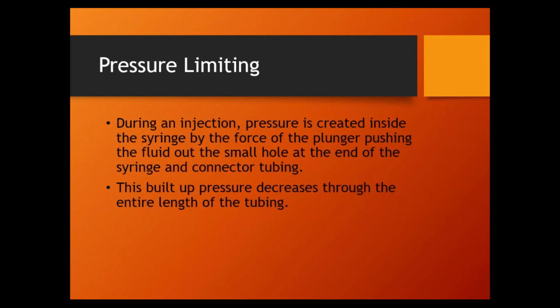pressure limit. Now, the pressure limit, people get the idea that, well, the pressure limit is sort of a safety device for the patient. It is, but it isn't really, right? It's a safety device to keep our syringe from exploding during the actual injection, okay? So, every injection, what we will do is we'll say, okay, don't go over 600 PSI. This one will actually go up to 1200 PSI.